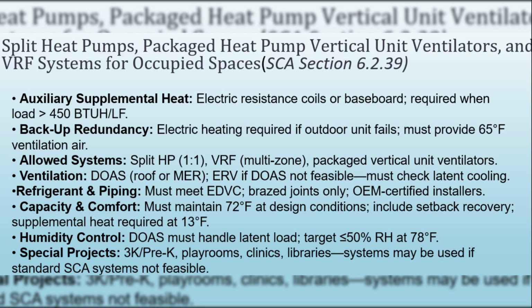If ceiling heights don't allow a central DOAS, a local ERV can be considered, but designers must ensure the terminal units provide enough latent cooling since ERVs don't handle moisture removal. Other requirements include: refrigerant charge must not exceed ASHRAE 15 EDVC limits, all refrigerant joints must be brazed, no press fittings allowed, condensate pumps must be provided, and VRF installations must be performed by OEM certified installers. For smaller buildings under 20,000 square feet, ceiling-mounted or closet-mounted ducted VRF units may be used, but larger schools must use closet-mounted units to avoid excessive ladder-based maintenance.